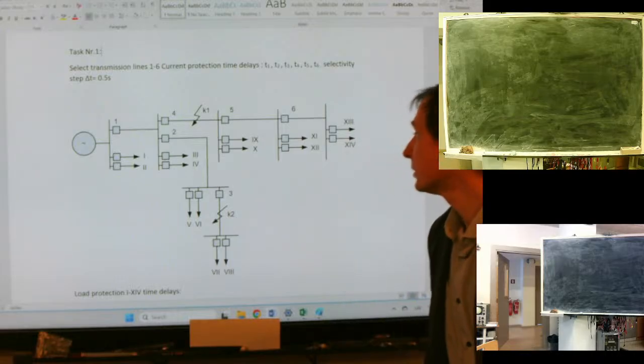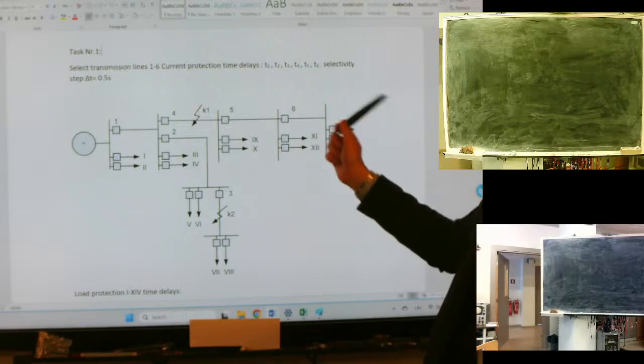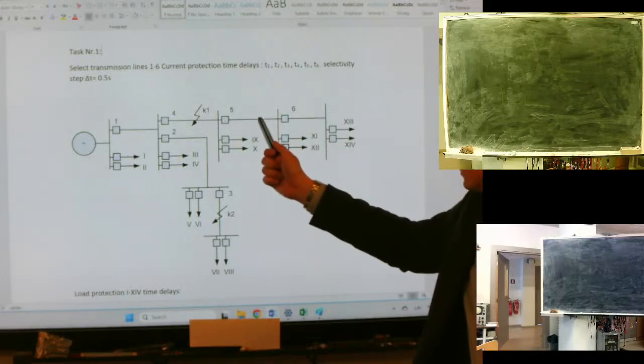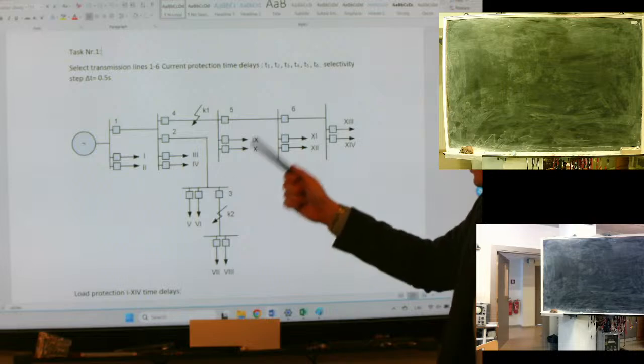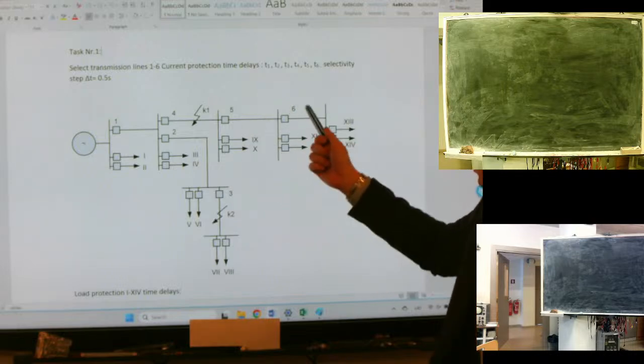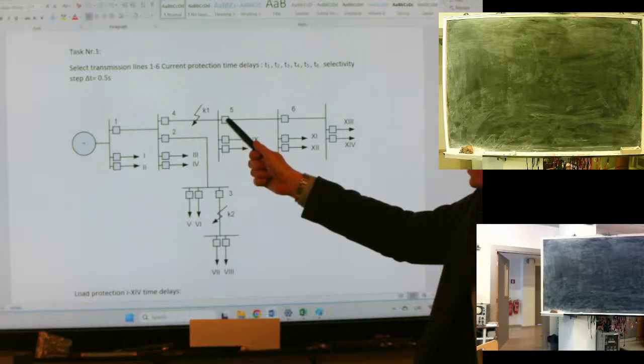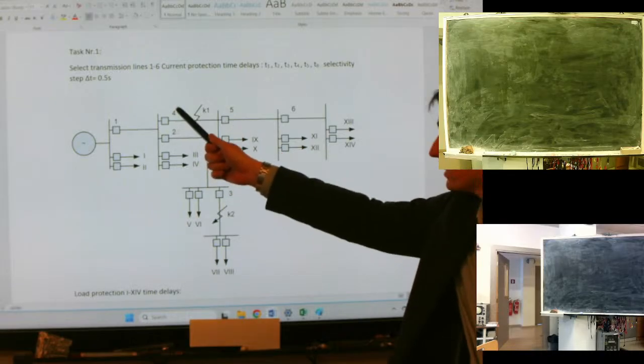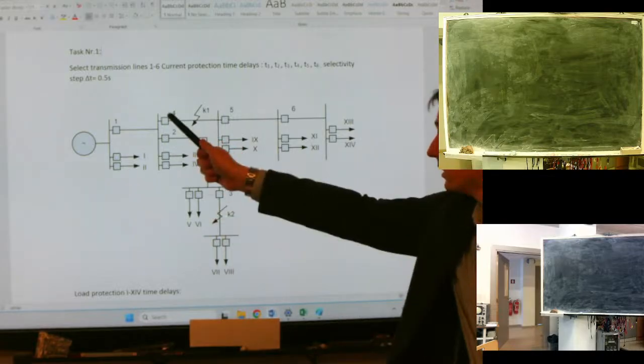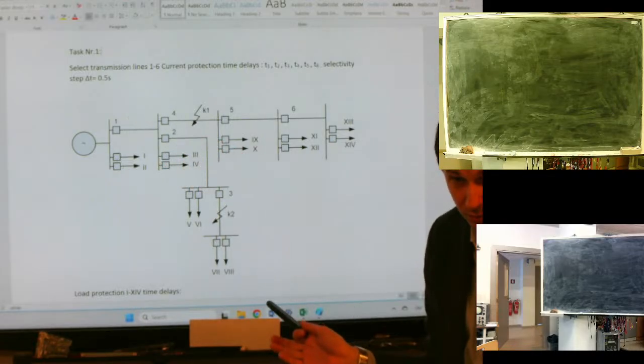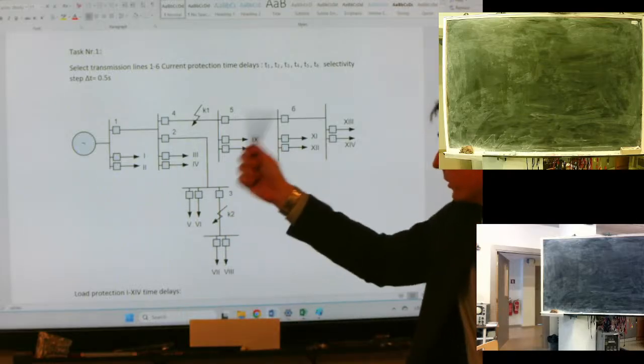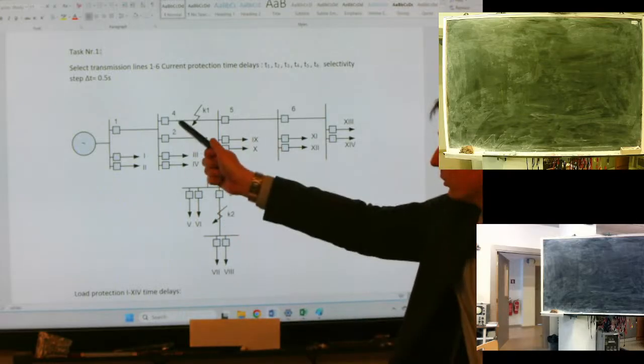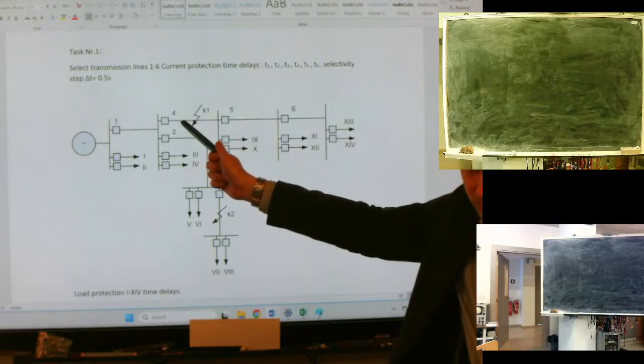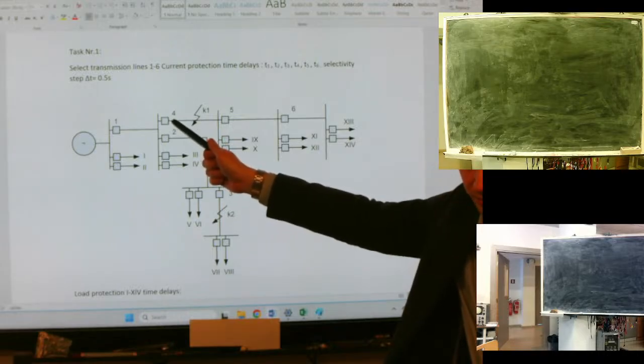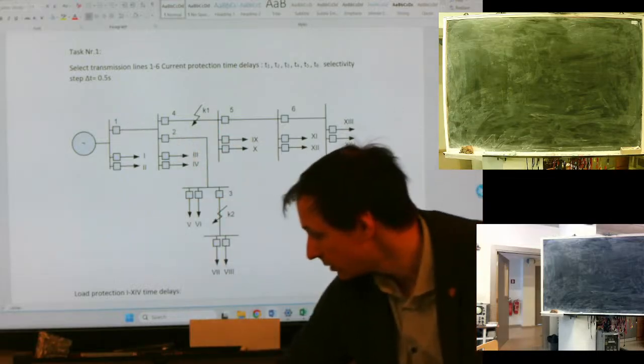In this case, when we start design for this branch, so the same logic, we could put 0 here, plus time step half a second here, 1 more step here, so 1 second here. So 1 second here and 1 second here, not good. So it means that when we have parallel branches, yes, we use the maximum time. For this reason we will take relay number 4 plus delta t, plus time delay.